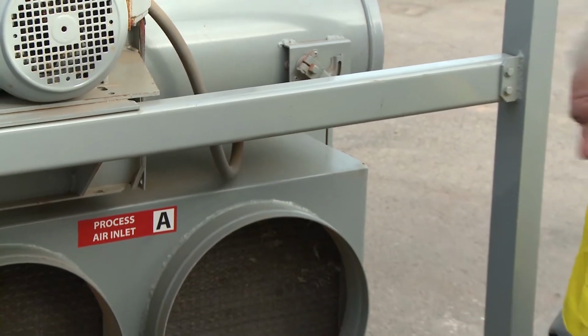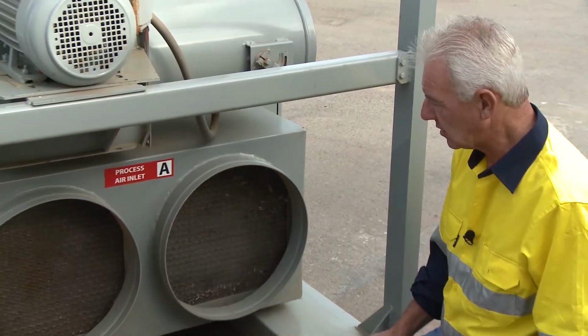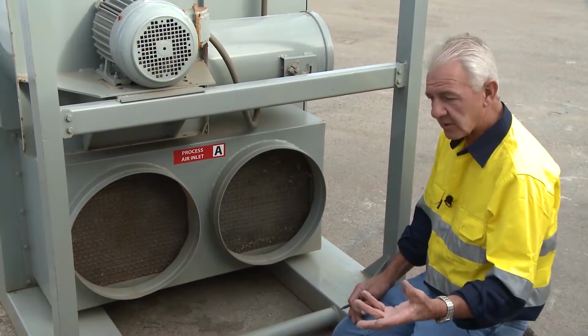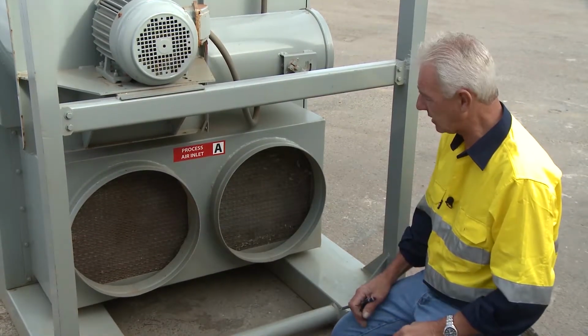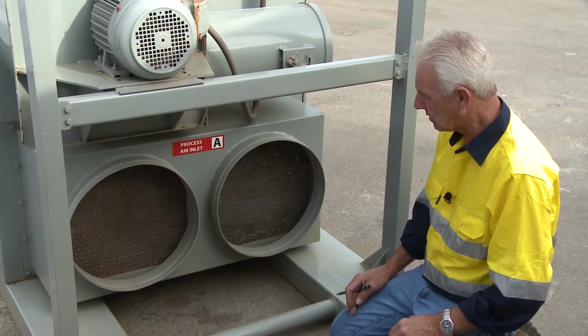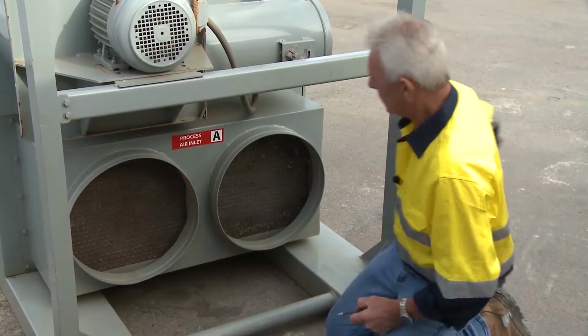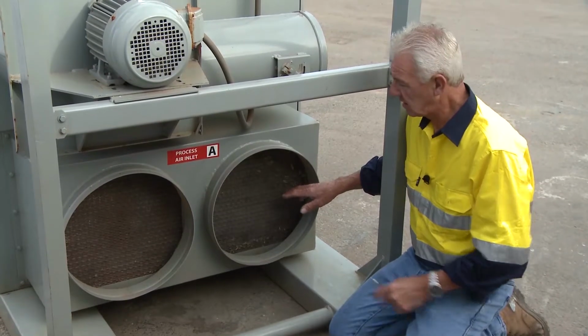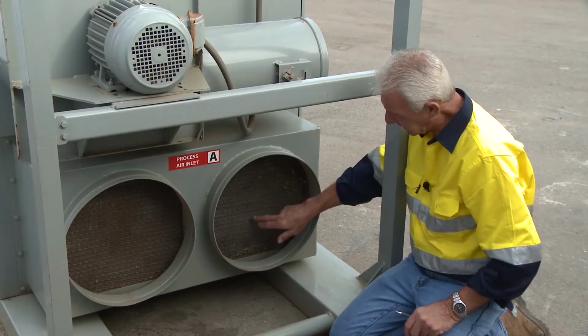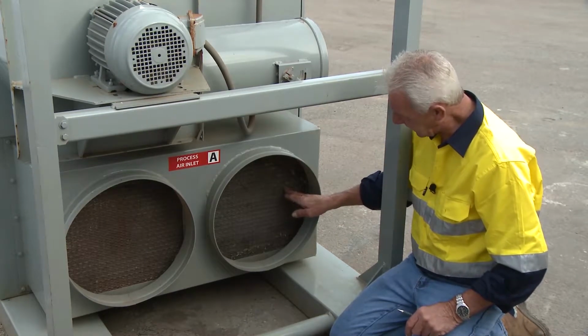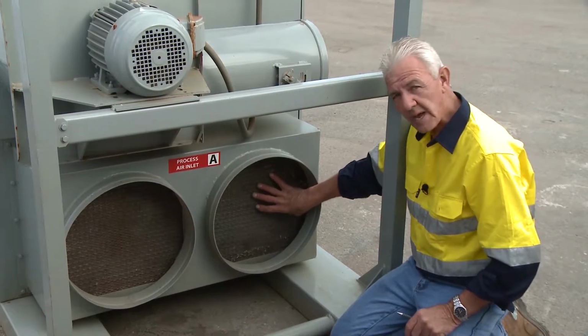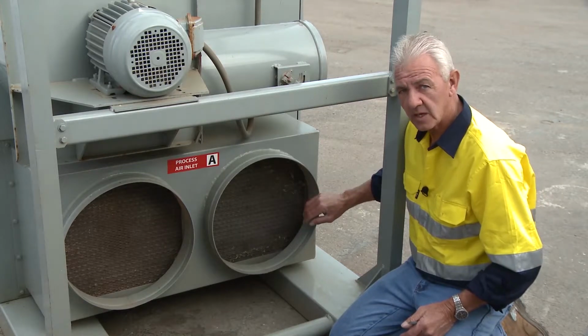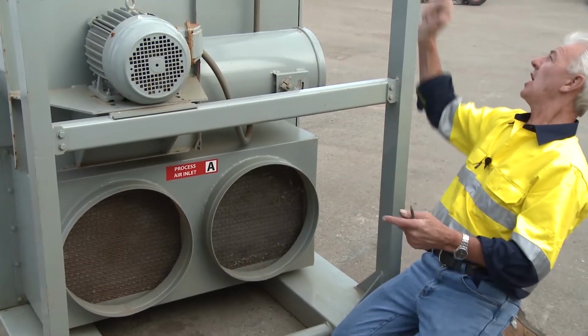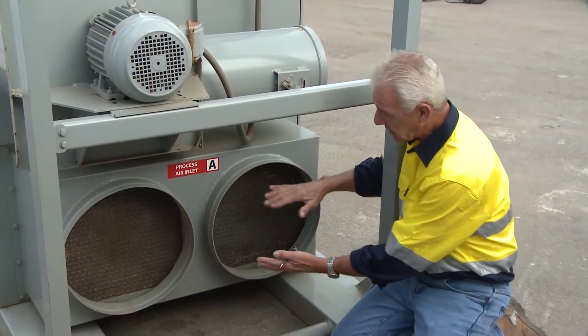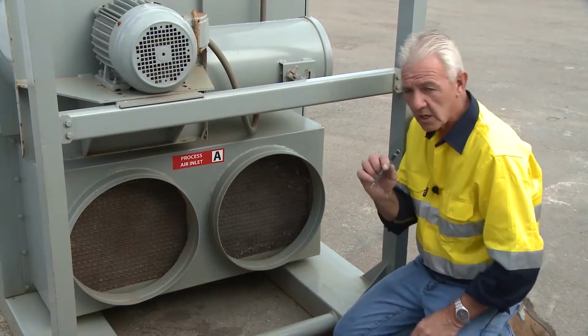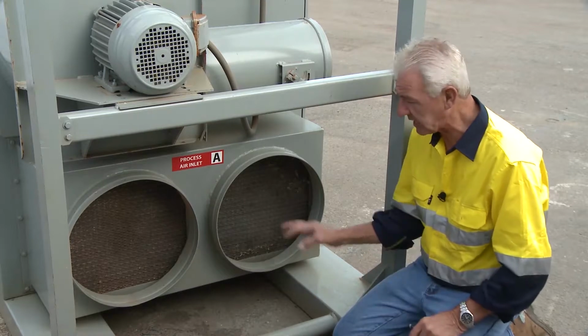What I have to be careful of here is, if there's dust within the encapsulation, or leaves and rubbish, things that can be easily picked up within a fanned, ducted environment, it'll be sucked into these particular vents and filters. So every night I have to take the ducting off and inspect these filter meshes for debris, because if it becomes overwhelming, it can dramatically affect the amount of air that travels through the machine. That's when you may get an overheat alarm or a high temperature shutdown, because it can't get the air through it. It's like drawing air through a straw, trying to suck and it can't possibly get the volume of air through.